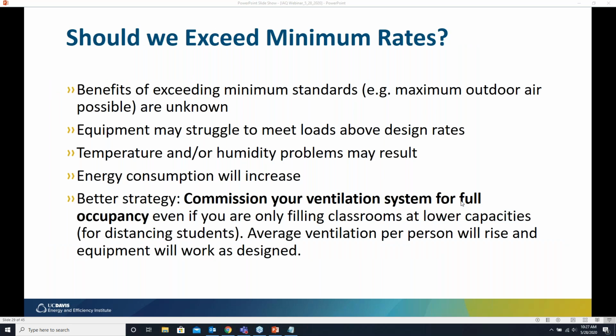So you'll see guidance from the CDC and from ASHRAE, you'll see suggestions to increase the amount of ventilation to the extent possible and potentially provide the maximum outdoor air that you can. As Rengie pointed out, it hasn't been determined that there's any amount of ventilation that will make the building, for example, completely safe. And so really the exact benefits of exceeding minimum standards are unknown. There are some risks to increasing ventilation rates above those minimums that I showed on the previous slide. Equipment may struggle to meet loads above the design rates. Temperature and humidity problems may result. And energy consumption will increase because you need to generally condition all that ventilation air that you bring into the space.